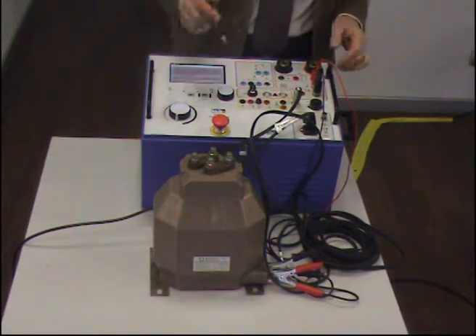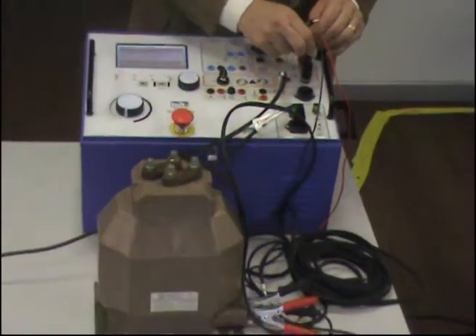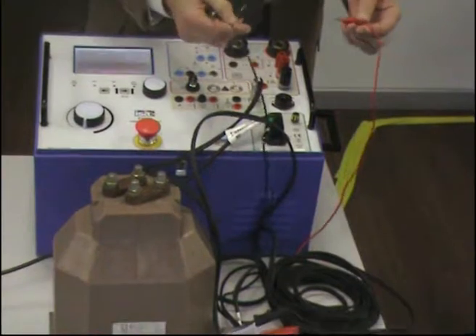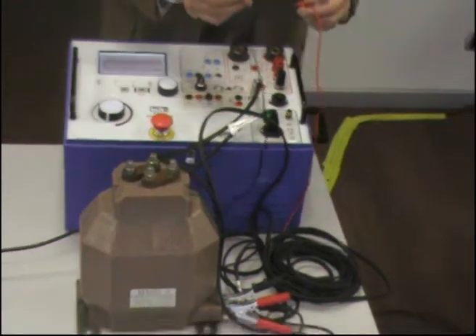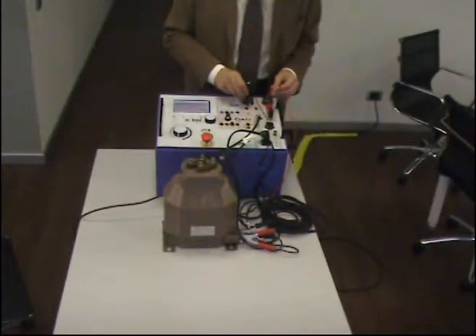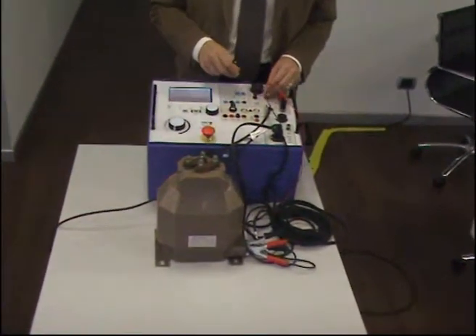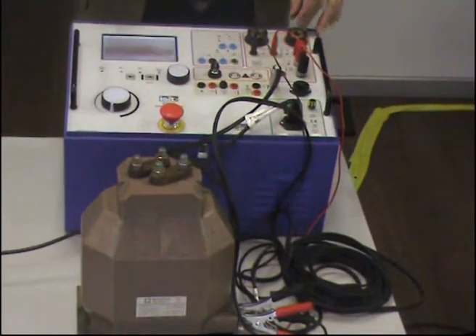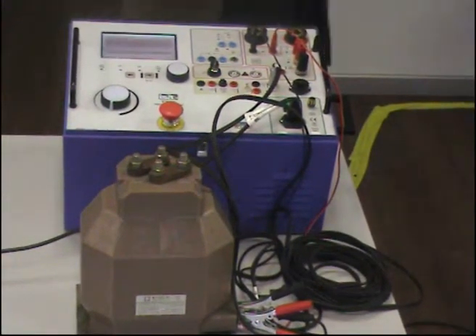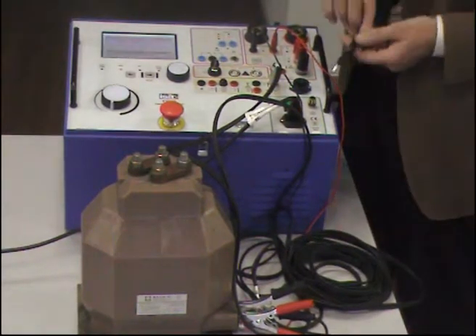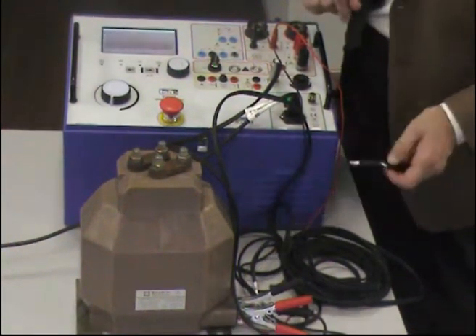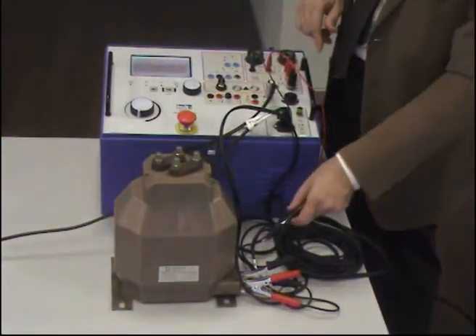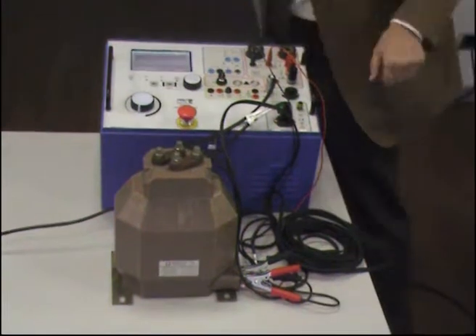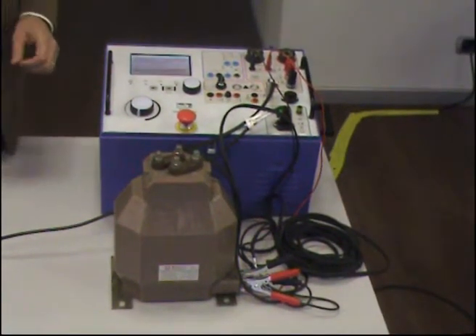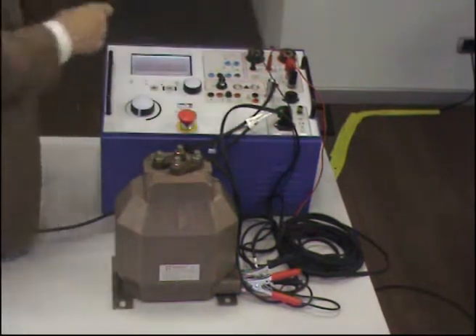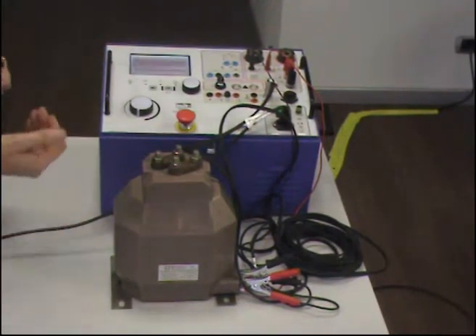Anyway, in our test, this is again my secondary side of the current transformer. I remove it from where it was, and I go here to this source of DC current. Being a resistance measurement, I also need to connect my voltage measurement input to the secondary winding so that I can measure the voltage and the current that I am injecting, and by the ratio I know the resistance.